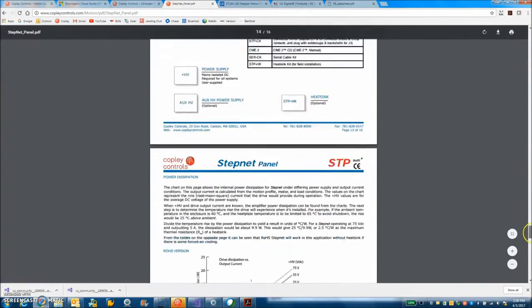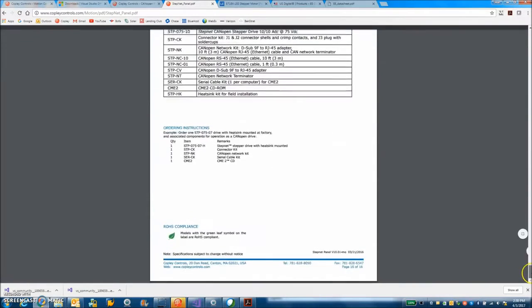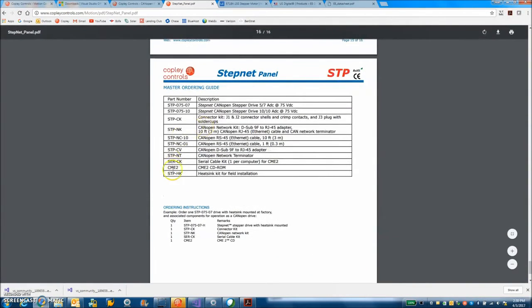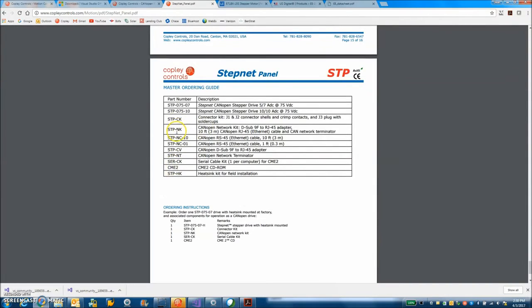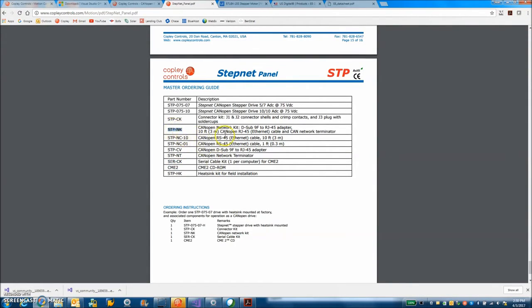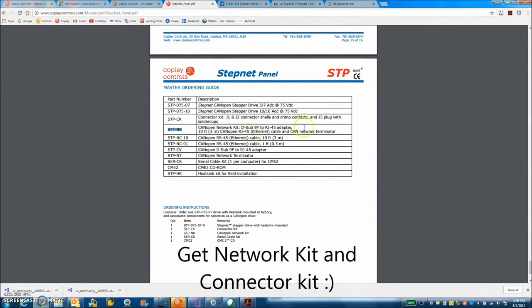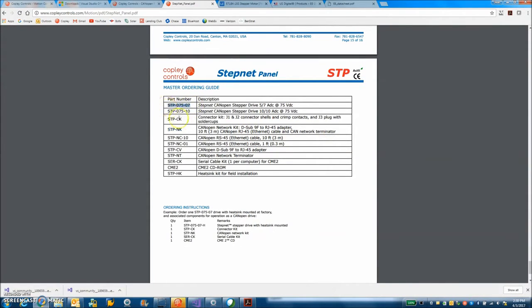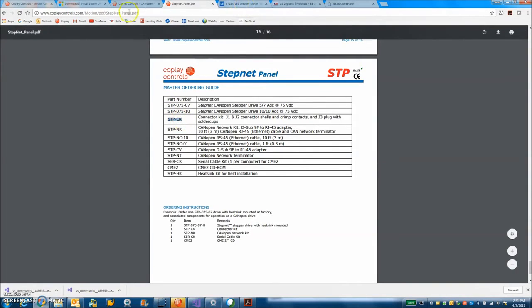On the last page of every data sheet are the accessory items. I'm going to use a USB to RJ11 instead of a serial cable kit. There's a StepNet NK network kit which comes with the adapter from 9 pin to RJ45 which plugs into the drive and a terminator, 120 ohms across CAN high and CAN low. And of course I'm using an STP 07507 and there's an STP CK connector kit so I can hook things up.